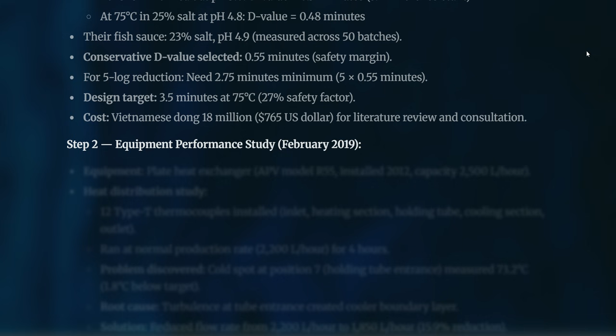All right. Now they move to step two, which is the equipment performance study. They did that in January, now in February, the second month. The equipment is a plate heat exchanger, APV model R55, installed in 2012, capacity 2,500 liters per hour. The heat distribution study is the following. 12 type T thermocouples installed, including inlet, heating section, holding tube, cooling section, and outlet, and run at normal production rate of 2,200 liters per hour for 4 hours.